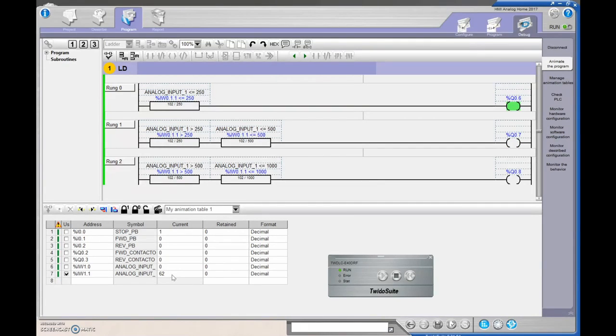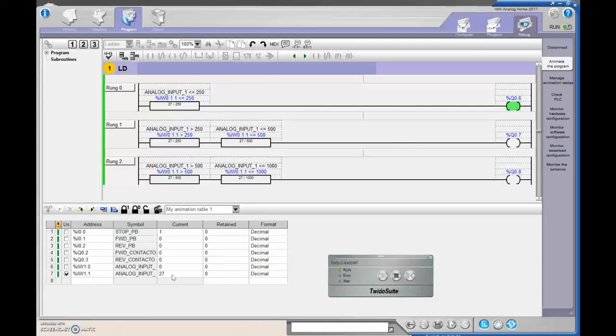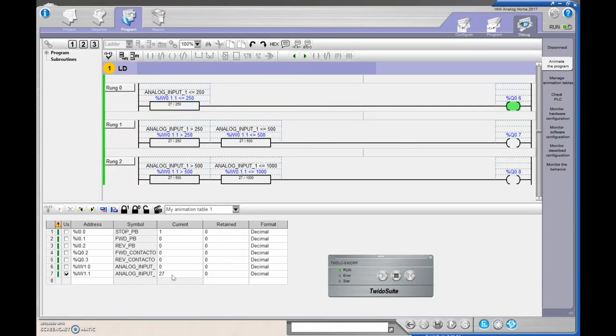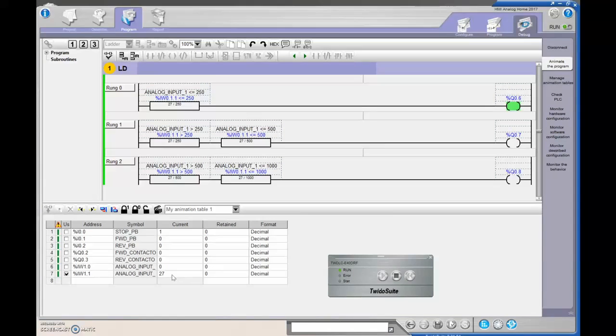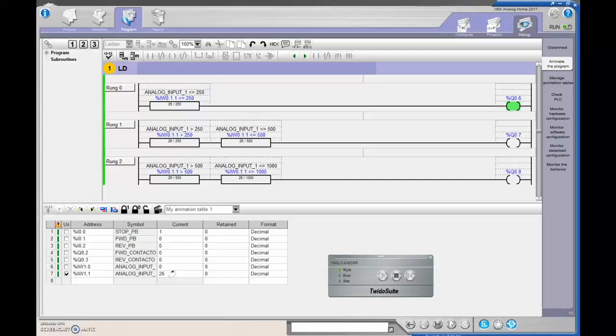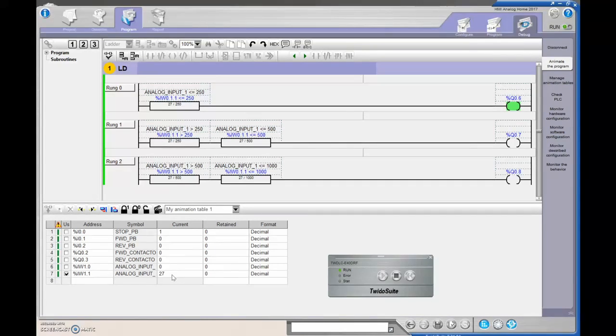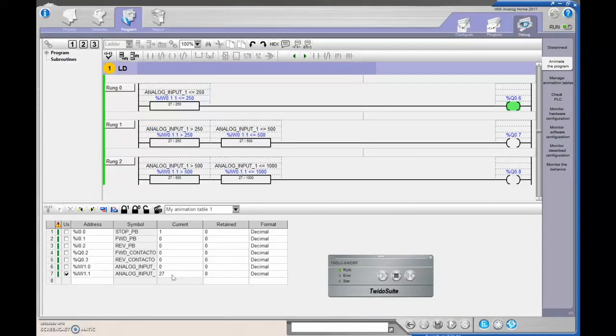And then from there, all the way down to zero. And I can't get all the way down to zero right now. I believe there's a potentiometer on the PLC that I can play around with. So I can zero that input. But right now, I'm getting 0.27 volts for when the piece of metal is directly in front of the sensor there. Awesome. Let me stop the video here and I'll show you the voltage change. And we'll do a picture-in-picture so you can see the voltage change on the meter and how that's changing on the actual program here.